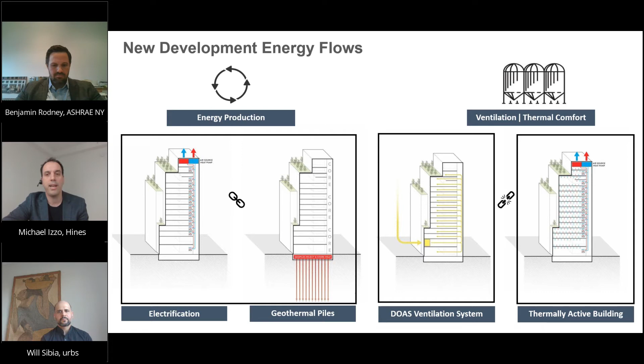Put that graph on the left, because if you dive into that graph a little bit more, what it tells you is that we do not need very hot and very cold energy sources within our buildings. You know, the days of using 180-degree water to heat the building, you don't need 180-degree water to heat the building. We're using 95 degrees and 60 degrees on the chilled water side. And what that does is increase the efficiency of your heat pump to a very, very high level. So generally heat pumps, and we also have a dry cooler, 6 times more efficient depending what mode you're in.